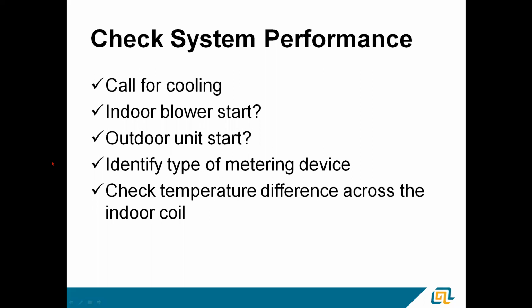Check system performance. Call for cooling. Get to the thermostat. I think what I see a lot of times is I'll ask technicians, "Have you looked at the thermostat?" And they say, "Oh no, I had the consumer turn it on for me." Well, you don't really know what mode it's in, what the set point is. So I honestly believe this is something that a technician should look at when he's there. Make sure that the indoor blower starts. Make sure the outdoor unit starts.